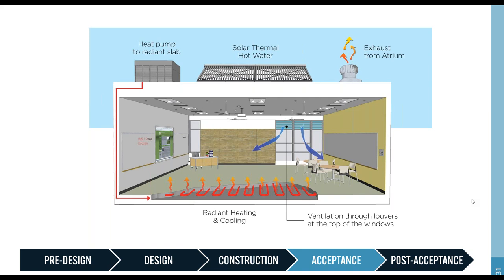So it's a perfect example that even the best design does not mean that the project is going to occur the way it's intended to, and that all those energy savings and occupancy comfort items will automatically occur. Luckily for us, we were able to get involved in this. We were able to help the project get back on track. And now the project is under yearly monitoring through a monitoring-based commissioning process to track energy to make sure that things continue to operate. And we've actually implemented a far more intelligent controls system than was originally in place.